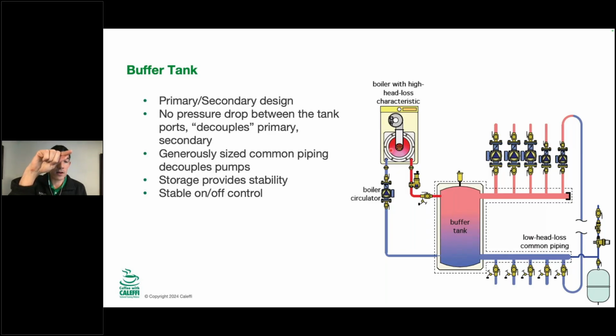And then the mod cons got better at the turn down ratio. So now they're going down to a 10-to-1 turn down or something like that. We don't really need the buffer tank as much. I'll go through the sizing piece. And now with heat pumps, because they can't quite do a 10-to-1 turn down or something that a mod con can do now, buffer tanks are starting to come back a little bit. So buffer tanks have been up and down. I'll show you how you would know if a buffer tank is a good idea and what problems it would solve and how to size that.